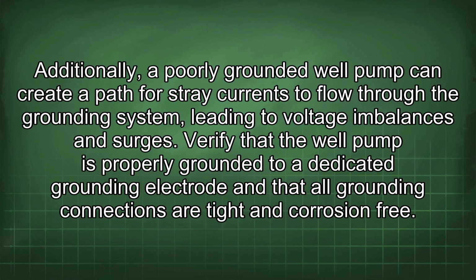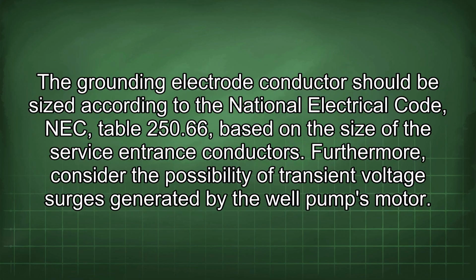Additionally, a poorly grounded well pump can create a path for stray currents to flow through the grounding system, leading to voltage imbalances and surges. Verify that the well pump is properly grounded to a dedicated grounding electrode and that all grounding connections are tight and corrosion-free. The grounding electrode conductor should be sized according to the National Electrical Code, NEC, Table 250.66, based on the size of the service entrance conductors. Furthermore, consider the possibility of transient voltage surges generated by the well pump's motor.